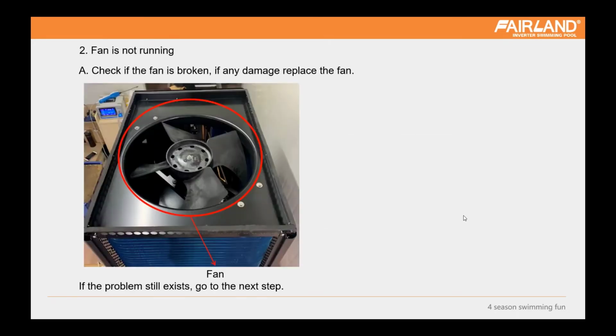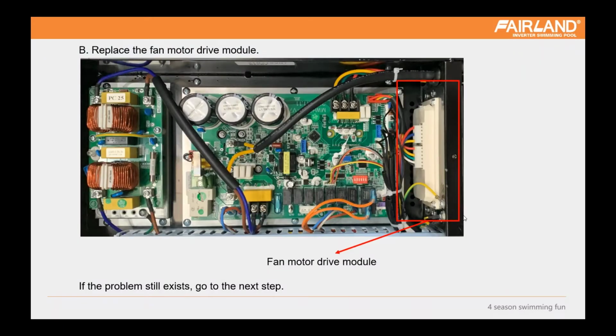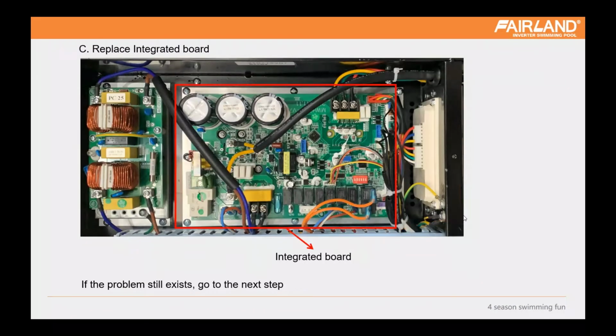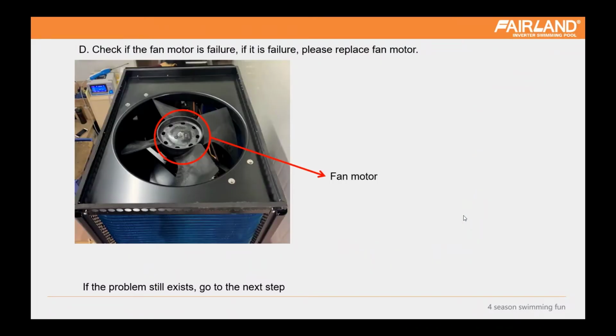For the fan running, we will check everything. Just open the top cover to see if the fan blade is blocked, damaged or broken. Normally it will not happen. So the fan blade is fine. Then we will replace the fan motor drive module. Next we will replace the integrated board. Finally we'll replace the fan motor. This is the final step because the fan motor is always top quality. The problem is normally from the integrated board or the fan motor drive module.